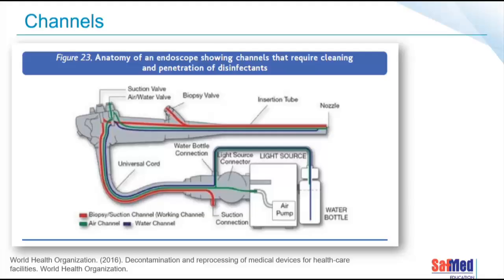Looking at our next line, if you have a look at the red line, that is the suction biopsy line. And it's very important that we brush the insertion part of the red line as well as from the control body down to the tip of the scope. Both sections must be brushed.